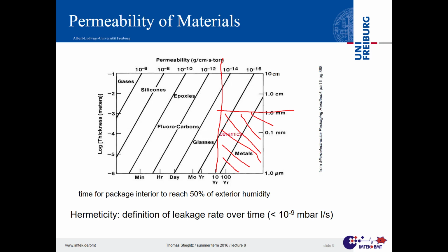If you would do that for every device you manufacture, that will mean every device that should be sold should go for 30 days in tests, just to see if it's tight or not, if it's watertight. And this is something that is not feasible for manufacturing. If you make whatever 100 pieces or 1,000 pieces per day, then you would need 1,000 of those very expensive machines in parallel.